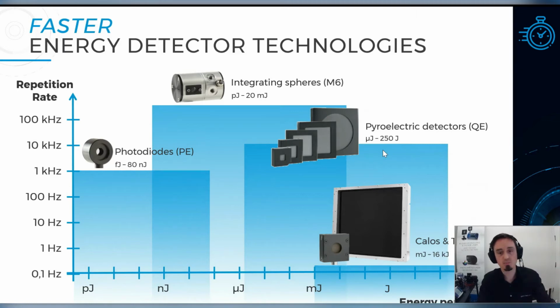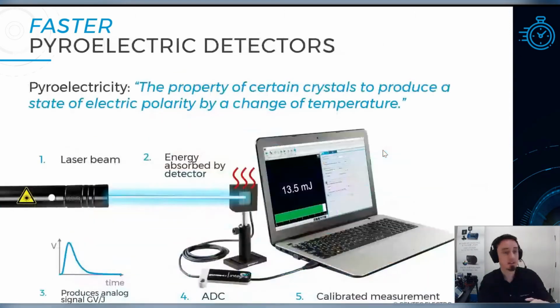Okay, so let's spend some more time on the QE series, the pyroelectric sensors. First, how does that work? Pyroelectricity, in a nutshell, is a property of certain crystals to produce a state of electric polarity by a change of temperature. The change of temperature is brought by the laser beam, the pulse of energy that comes out of the laser output. So you have a laser beam hitting the surface of this pyroelectric sensor. The heat is absorbed. Then naturally the crystal produces a voltage that's proportional to the amount of energy contained within the laser pulse. Then you have an ADC converting this analog signal to a digital signal going to the computer to provide a calibrated measurement.